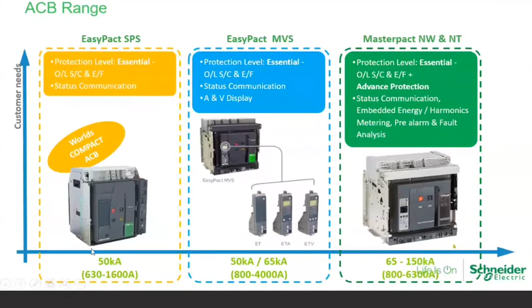After this, I will show you the EasyCom module, and how it allows the user to get status and communication on the Modbus RS485. This is in front of you. You can connect 3 breakers for the status. In the status, you can read on-off, trip and ready-to-close status for all these 3 breakers, and it will give the data on the Modbus RS485 communication, and it also has a control function.